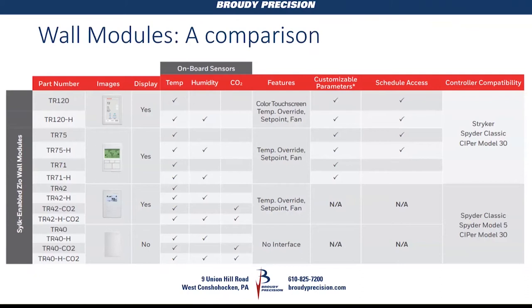You also have the non-configurable TR-42 series, available with just temperature, temperature plus humidity, CO2, or humidity and CO2 with temperature. And then the TR-40 without a display, with the same flavors. These are all Sylk-enabled — just two wires from sensor to controller, so you're not using up any I/O on the controller. The TR-40 series can only be used on the Spider Classic PUB/PUL, the Spider-5, and the CIPR-30.